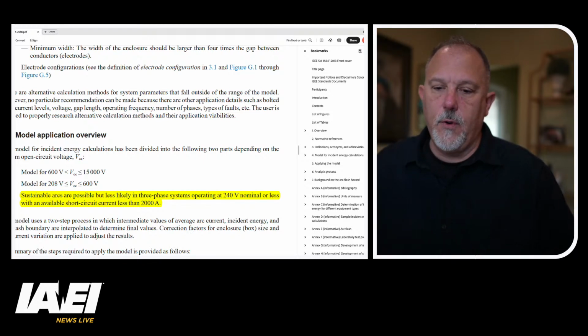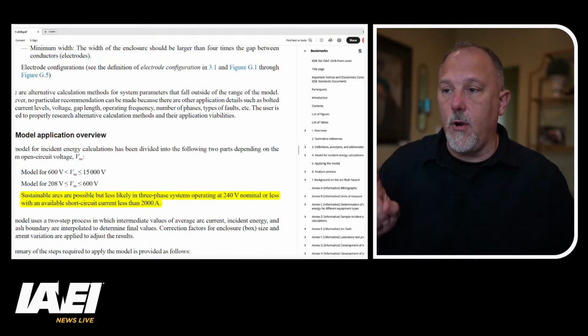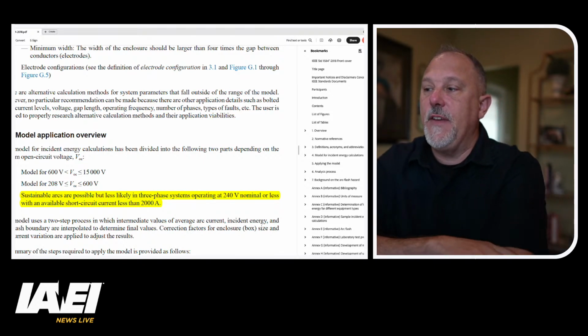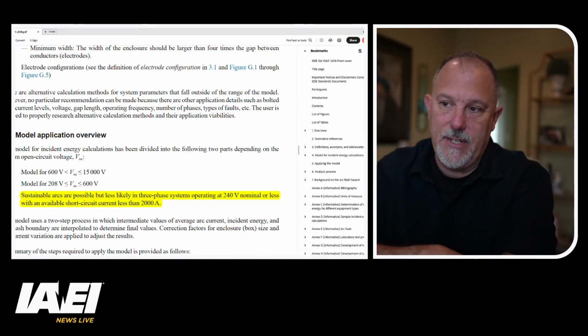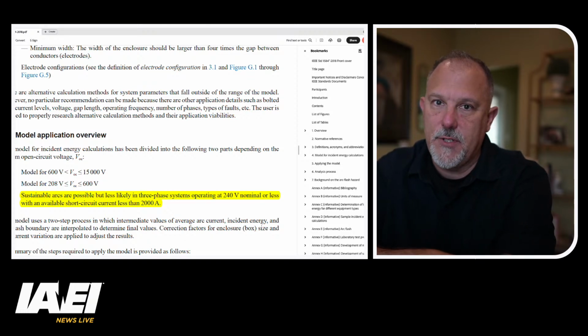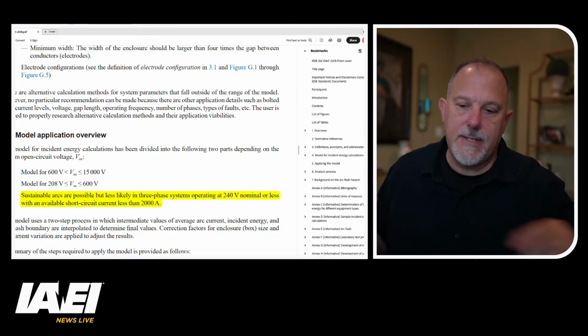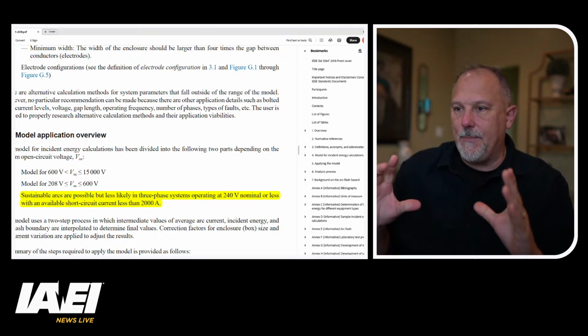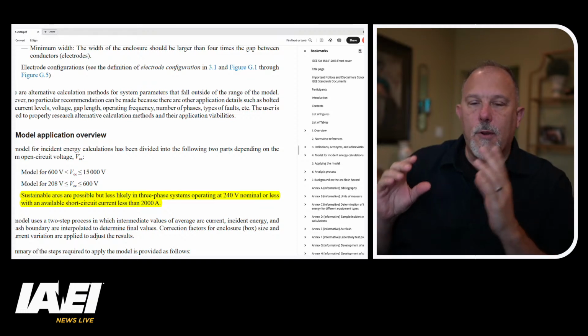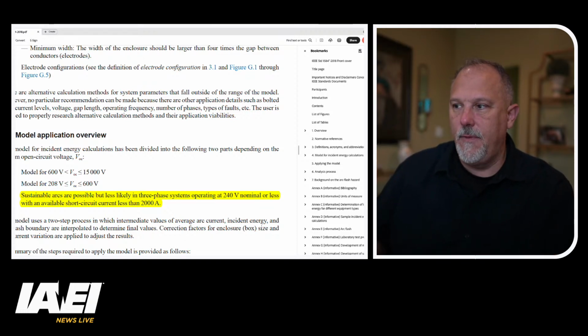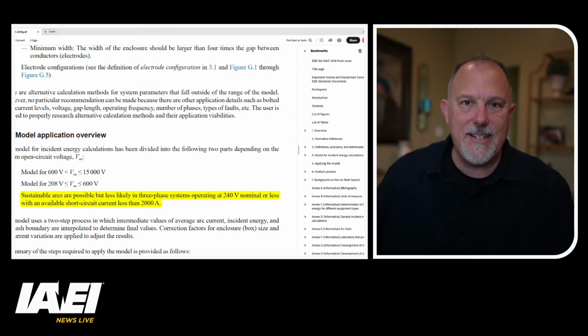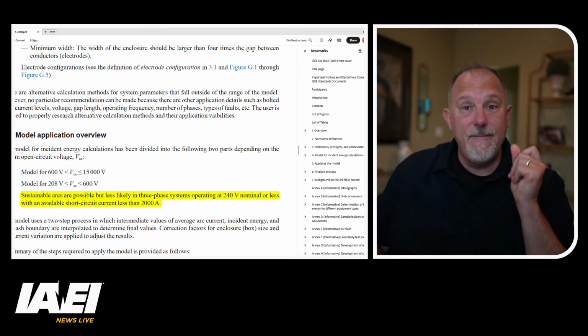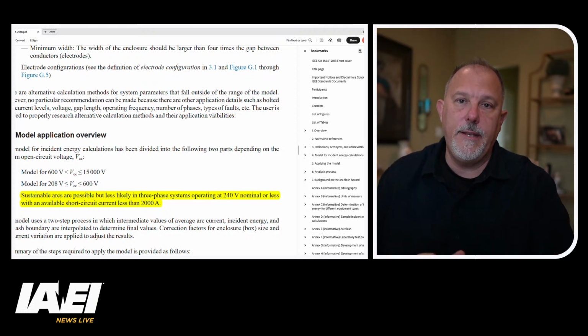Here's what IEEE 1584 says: sustainable arcs are possible, but less likely in three-phase systems operating at 240 volts nominal or less with an available short circuit current less than 2,000 amps. In my opinion, I would look out for an exception in the future along those lines: the requirements of 110.16 shall not apply for systems 240 volts nominal or less where an available short circuit current is less than 2,000 amps. That's my prediction. I think that will come next year.